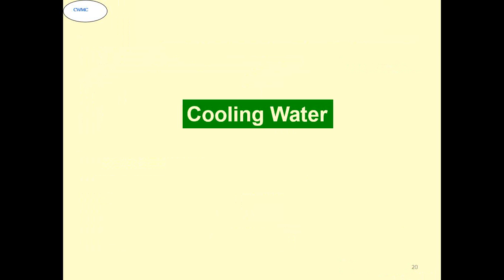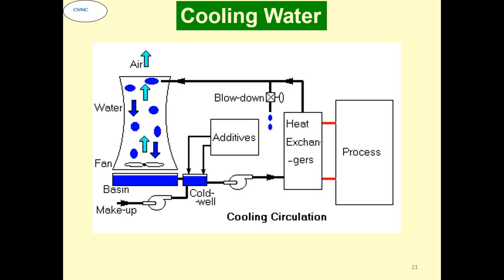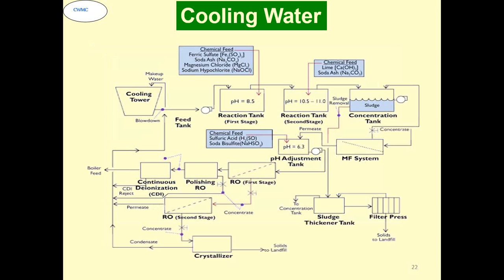Now coming to cooling water. In a typical cooling water system that you see, there's a cooling tower, there are some additives, heat exchangers, and a process. The process can be anything. It can be the power sector, it can be the chemical sector, steel, cement, anything. Nowadays, because this is going to be one of the requirements, the upcoming thing is the usage of municipal treated sewage water as cooling tower makeup water. So this is the typical cycle for that.